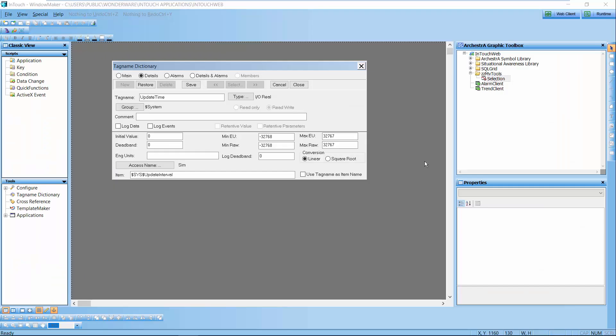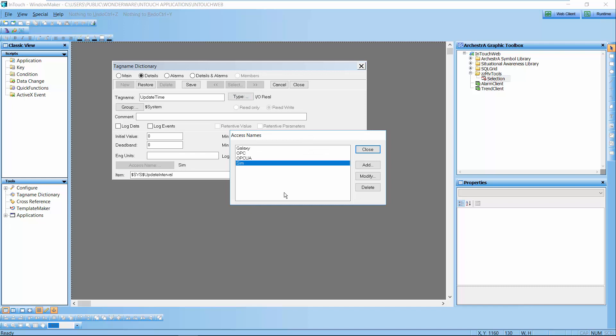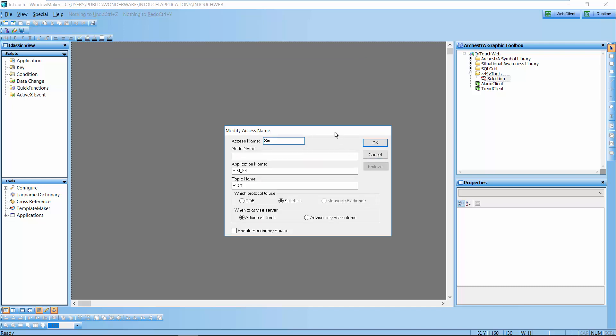So in my InTouch application I created a variable called UpdateTime, it's an I/O Real and the access name is Simulation.IsSim and that's pointing to my simulation I/O server. This could be an Allen Bradley driver, a Siemens driver, a Modicon driver - all Wonderware drivers or OI servers or DA servers have this property available to us to be able to change this variable at runtime.